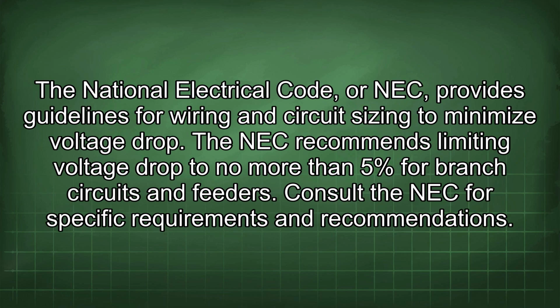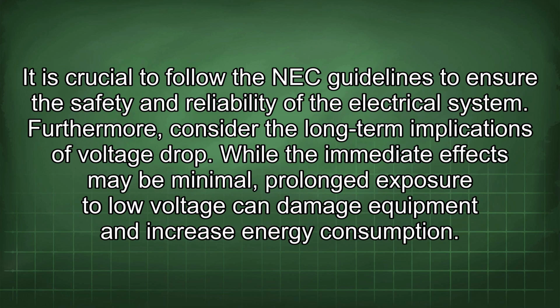The National Electrical Code, or NEC, provides guidelines for wiring and circuit sizing to minimize voltage drop. The NEC recommends limiting voltage drop to no more than 5% for branch circuits and feeders. Consult the NEC for specific requirements and recommendations. It is crucial to follow the NEC guidelines to ensure the safety and reliability of the electrical system.